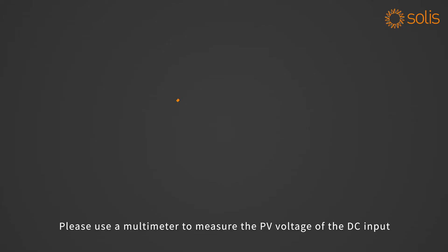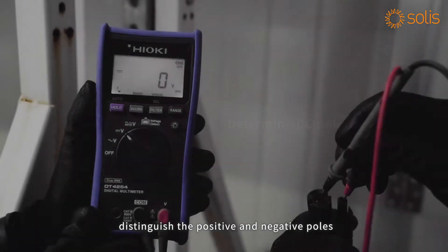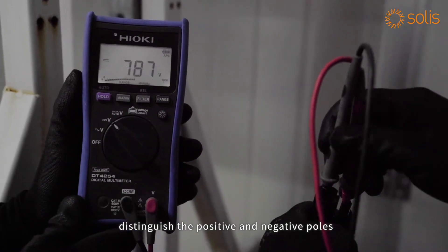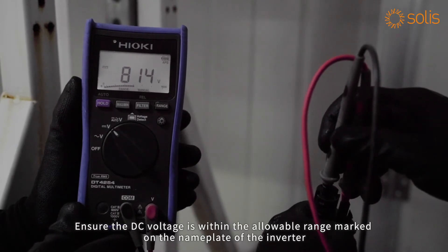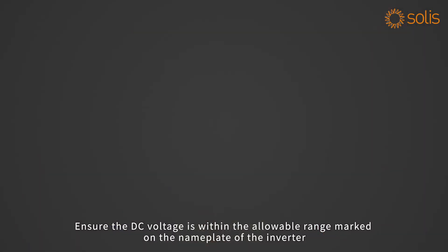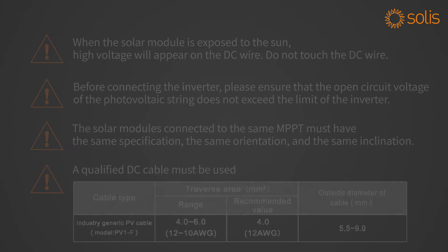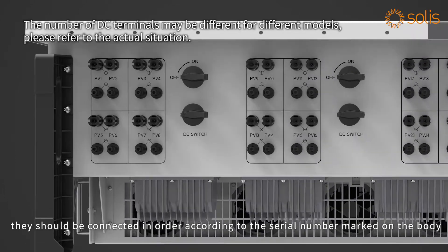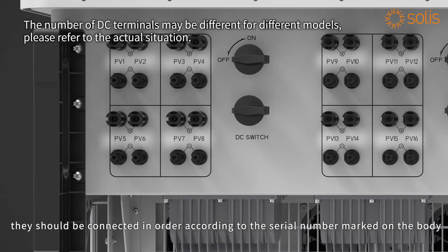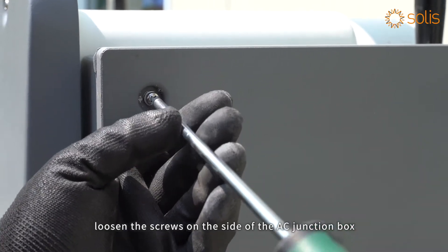DC side connection: please use a multimeter to measure the PV voltage of the DC input. Distinguish the positive and negative poles and ensure the DC voltage is within the allowable range marked on the nameplate of the inverter. Please refer to Solis's demonstration video for making the DC connection cable. When connecting DC cables, they should be connected in order according to the serial number marked on the body.